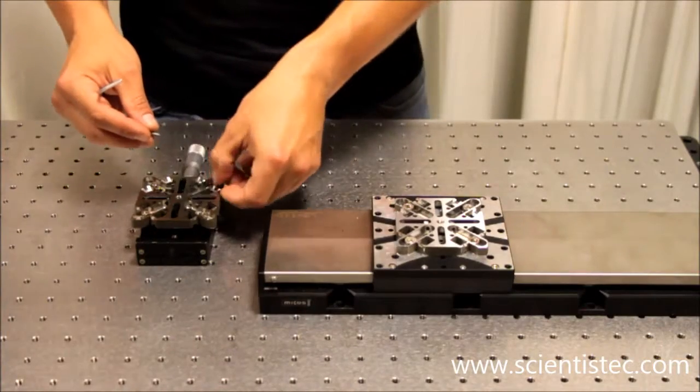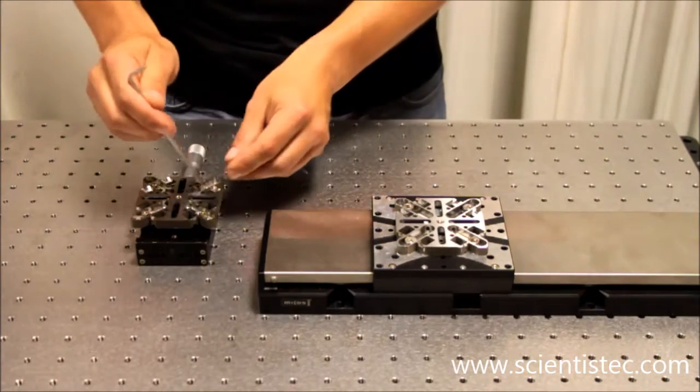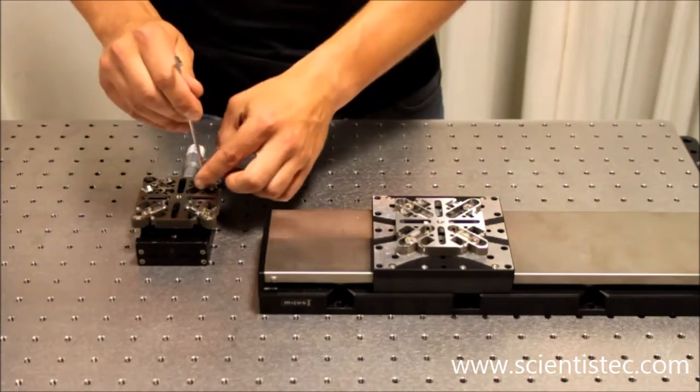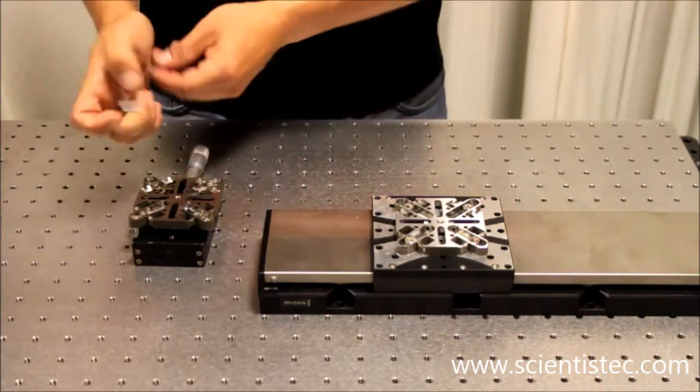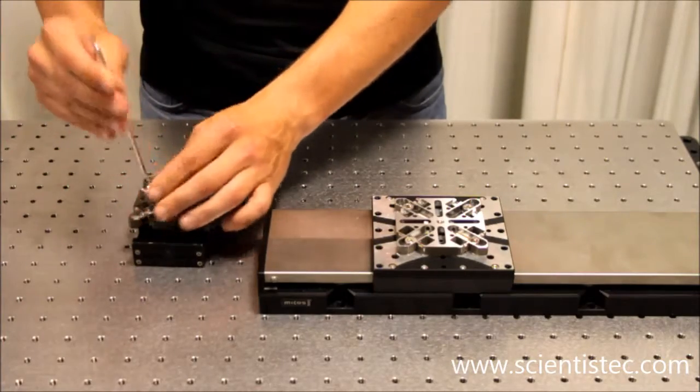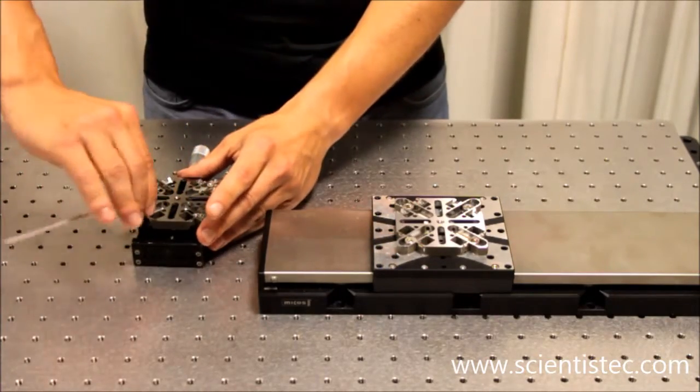As seen before, I tighten the screws slightly first until all screws are in position before I tighten the screws completely. Based on the position of the washers, the BeamLine adapter aligns itself optimally.